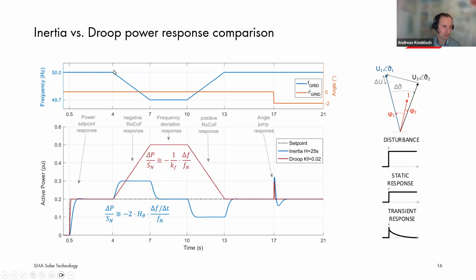Yeah. So if there is a frequency deviation from this reference value of frequency, then the inverter would provide an active power response that is proportional to the droop constant. And on the other side, we have the inertia control mode, where the active power response is proportional to the frequency gradient, so the rate of change of frequency, and an inertia constant H that is adjustable at inverter level. So we see both kinds of response are instantaneous, but with different response times or response behaviors regarding the frequency changes. The droop control provides a static response to frequency deviations, while the inertia response provides only a transient response to frequency deviations, but a static response to permanent frequency changes in that case.